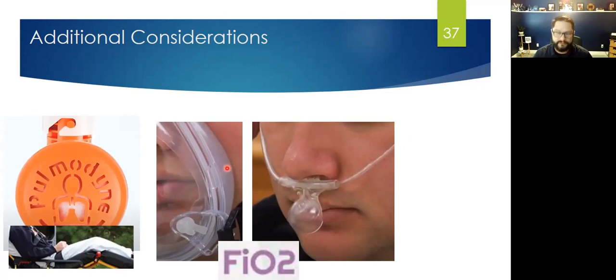If you don't believe that's enough, you can pop open one of these caps on the front of the mask and put some oxygen supply tubing on. And then there's an equation: 4 times whatever liter flow you set it at, plus 21% ambient air. Obviously it's got to be higher than 30%. If you don't give enough to be higher than 30%, it's going to use the 30% from the device. So if you put that at a higher flow, you could bring that FiO2 up significantly. They also have this other device called a trio that you can put on, but basically this is going to be your first line of defense to increase your FiO2 if you feel like you need to.